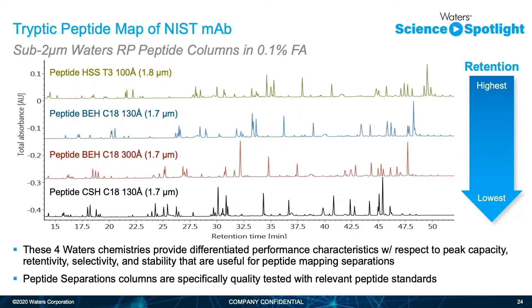Depicted here are the varying selectivities of each of the peptide particle chemistries — QC'd with a tryptically digested sample. Highlights include the increased retentivity by switching to the peptide HSST3, which has a 100 angstrom pore size, while the lowest retentivity is the peptide CSH at 130 angstrom. There are numerous selectivity differences between all four particles. The highest peak capacity for some peptides is provided by the peptide CSH. Comparable average peak capacities for the HSST3 and the BEH in both pore sizes are comparable. The peptide HSST3 is the best choice for small polar peptides because of its great retentivity.